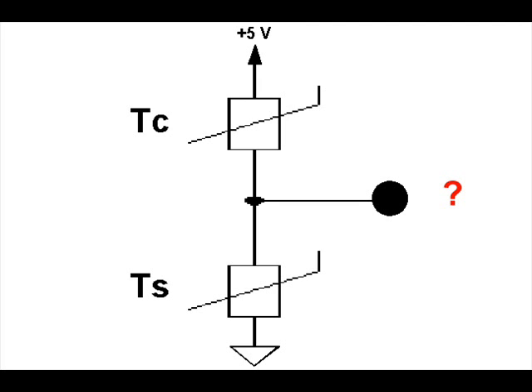The top sensor is the collector thermistor and the bottom sensor is the storage temperature. For now, let's say they are both at the same temperature. Now, what will be the common junction voltage? If both sensors have the same temperature, the resistance will be equal, and the voltage at the common junction of the divider will be half the supply voltage, or 2.5 volts. That's right.